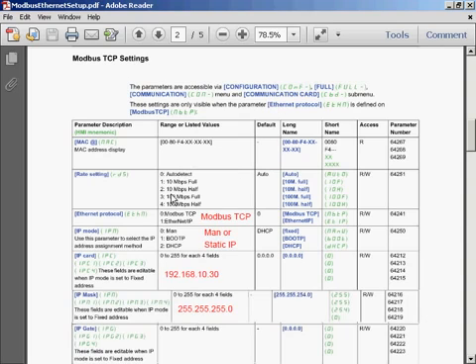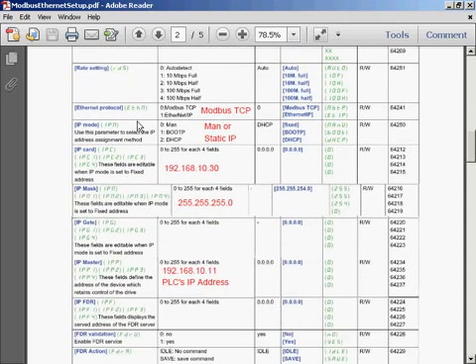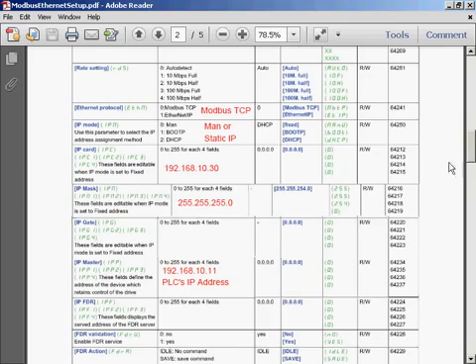You'll notice the following settings. We are going to make sure the Ethernet protocol is set to Modbus TCP. We have our choice. We're going to set a static IP address in there of 192.168.10.30. I'm going to give it the subnet mask. And since we're doing Modbus TCP, I am going to configure the PLC, which is the IP master. This 192.168.10.11 is the PLC's IP address.